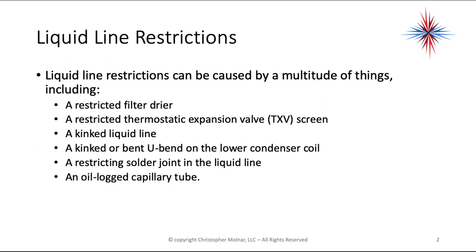For a restricted thermostatic expansion valve screen — that's the screen on the inlet of the TXV — it's a bit more difficult to find because you normally have a temperature drop across the TXV. You're going to have to recover the system or pump it down and inspect that screen if you suspect it's the issue.